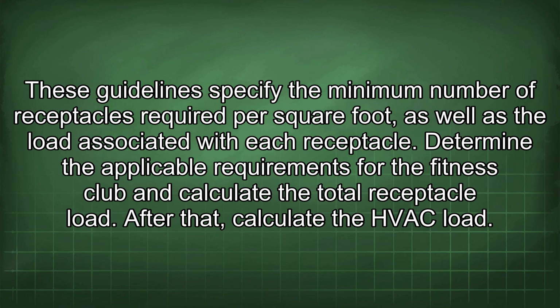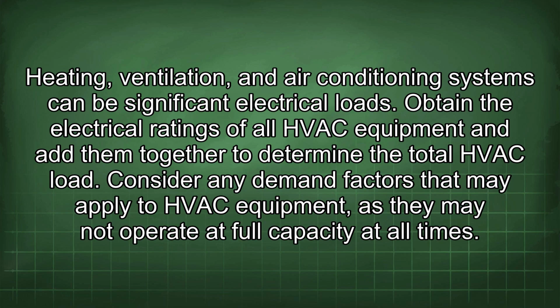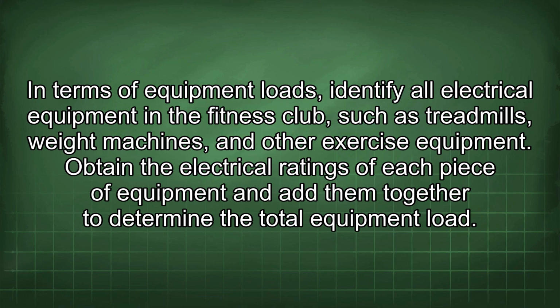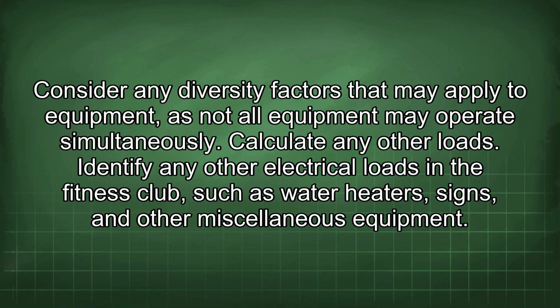After that, calculate the HVAC load. Heating, ventilation, and air conditioning systems can be significant electrical loads. Obtain the electrical ratings of all HVAC equipment and add them together to determine the total HVAC load. Consider any demand factors that may apply to HVAC equipment, as they may not operate at full capacity at all times. In terms of equipment loads, identify all electrical equipment in the fitness club, such as treadmills, weight machines, and other exercise equipment. Obtain the electrical ratings of each piece of equipment and add them together to determine the total equipment load. Consider any diversity factors that may apply to equipment, as not all equipment may operate simultaneously.